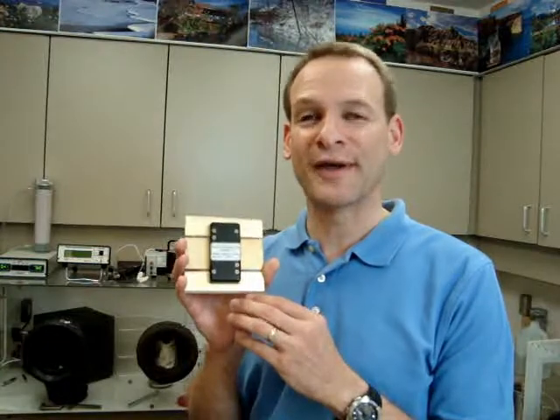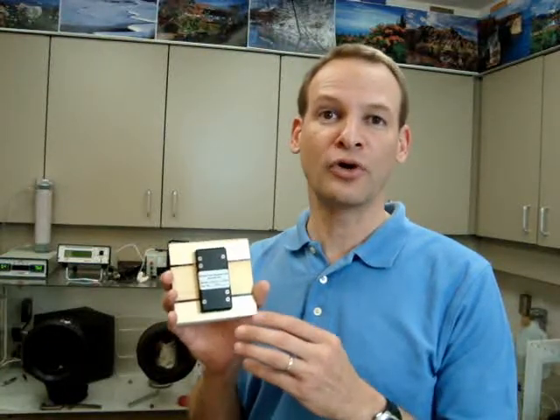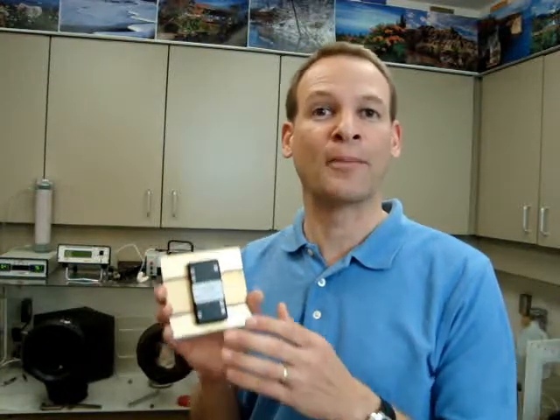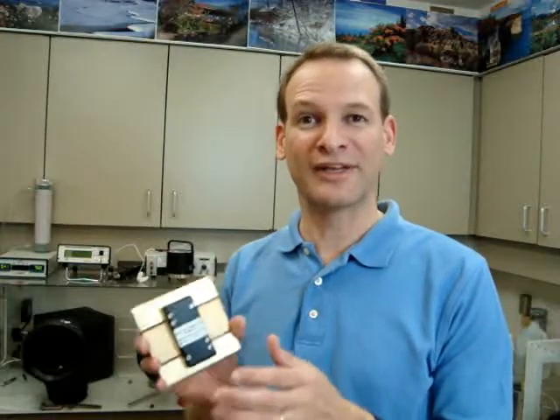Now, one thing to keep in mind with the STM-2 or even the STM-1, they are not used to calibrate the system. They're only used to test and verify the operation of the static decay meter.